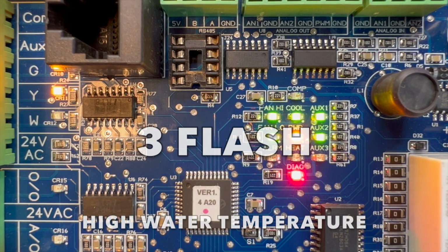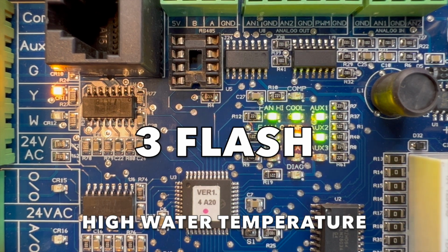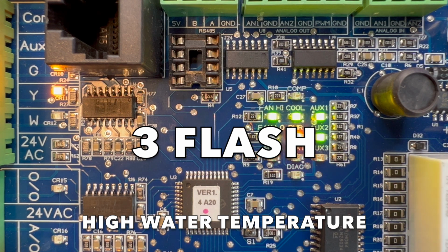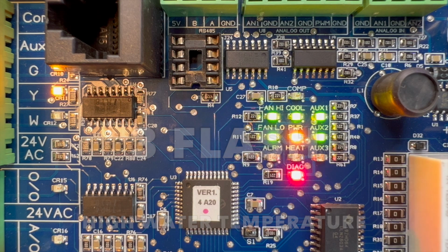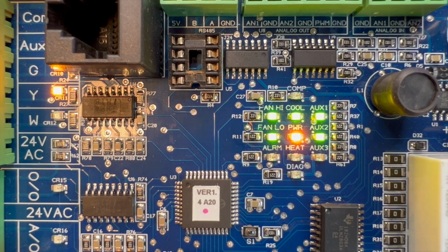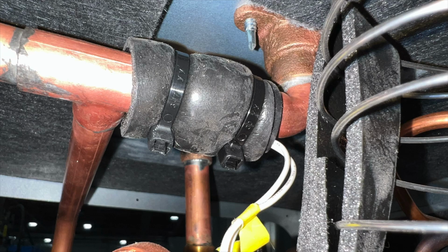3 flash, high water temperature. The optimum loop temperature is between 85 and 125 degrees Fahrenheit. This fault will disable the compressor when the leaving water temperature goes above 140 degrees Fahrenheit. The unit will reset when that temperature drops below 120 Fahrenheit. This sensor is strapped to the leaving water pipe and insulated with Armaflex.